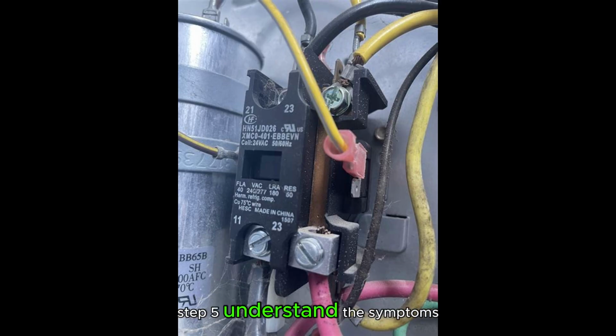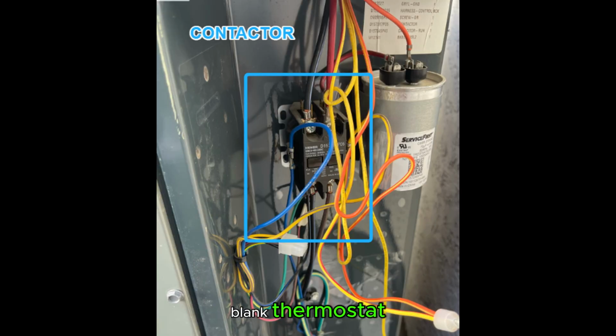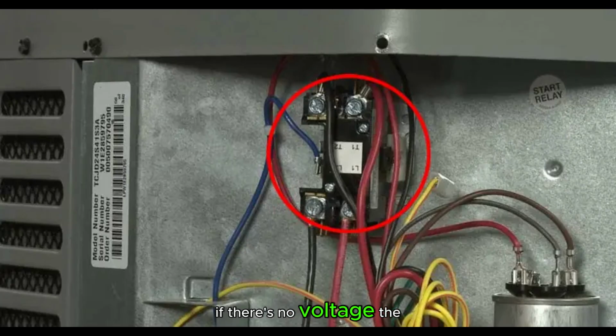Step 5. Understand the symptoms. Blank thermostat? Check for 24 volts between R and C. If there's no voltage, the transformer, the fuse, or a float switch may be open. System turns on but condenser doesn't. Check for 24 volts at Y and common when cooling is called. If no signal, check the thermostat. Condenser clicks but doesn't run? Check the contactor coil for 24 volts. If it's energized, then check the compressor and the fan motor.